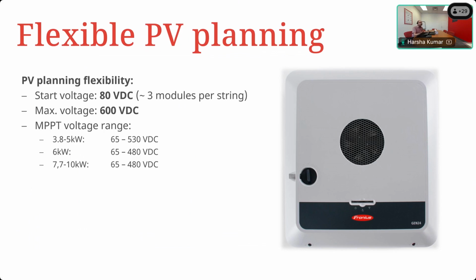But like I mentioned earlier, you always want to design the strings that you intend to work with to be higher rather than lower, simply because at higher voltages, the amount of current required for the same amount of power is lower. And if you can keep the current lower, typically your losses tend to be lower, and it makes for more efficient operation. And you'll also save on the cabling cost as well.